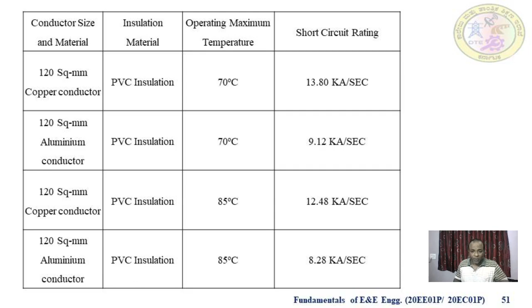A 120 square mm copper conductor, also with PVC insulation, holds up to 85° Celsius and has 12.48 kiloampere per second as its short circuit rating. And a 120 square mm aluminum conductor, also with PVC insulation, holds up to 85° Celsius, and the short circuit rating for that is 8.28 kiloampere per second.